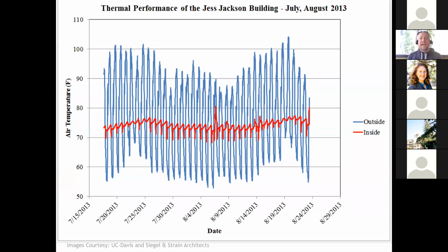This is actual data from inside the building. Again, no air conditioning in Davis, where outside temperatures regularly get over 100 degrees in the summer. This blue line shows outside air temperature, going down into the 60s and mid 50s at night, then up to 100 degrees during the day. We take in air at night, cool the building down, and let it ride. The red line is inside air temperature, and with no active air conditioning, we were able to maintain this building around 75 degrees year round.